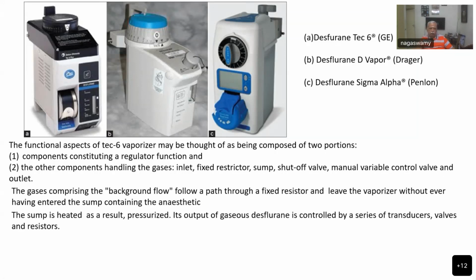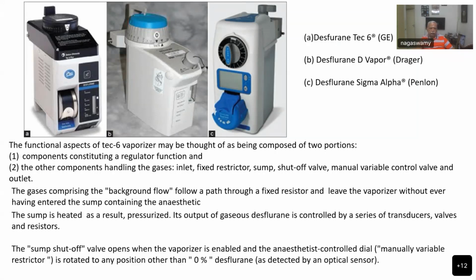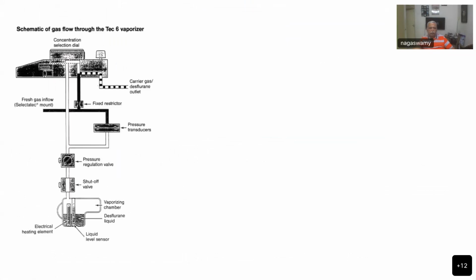It is pressurized and the output of gaseous desflurane is controlled by a series of transducers, valves, and resistors. The sump shut-off valve opens when the vaporizer is enabled and the anesthetic control dial, that is the manual variable restrictor, is rotated to any position other than 0% desflurane, as detected by an optical sensor in that dial setting, which controls the valve to fix the percentage of delivery. This is the schematic diagram of this desflurane Tec 6 vaporizer.